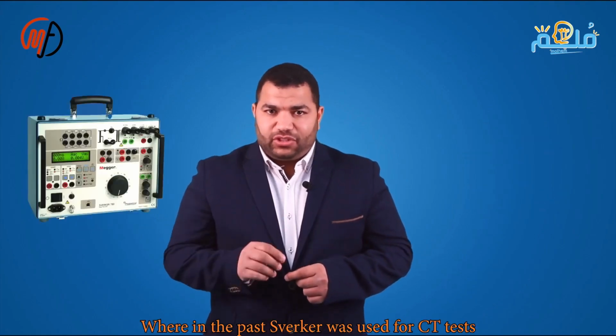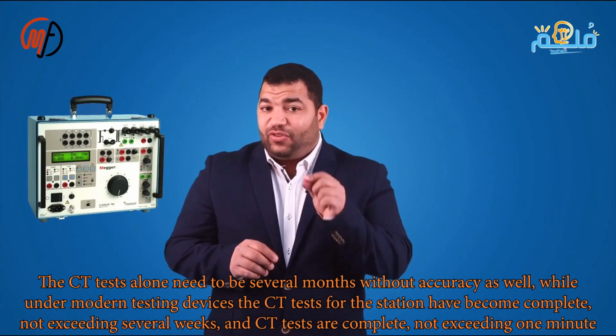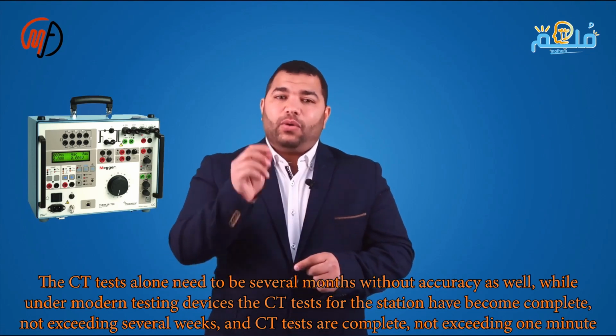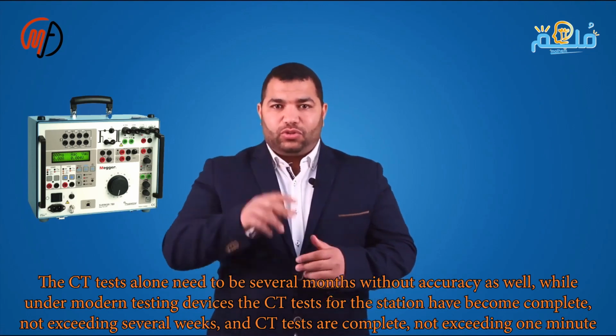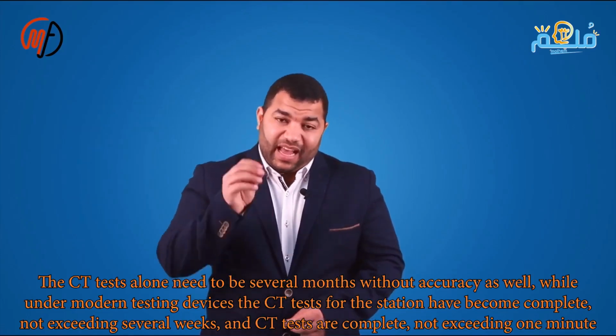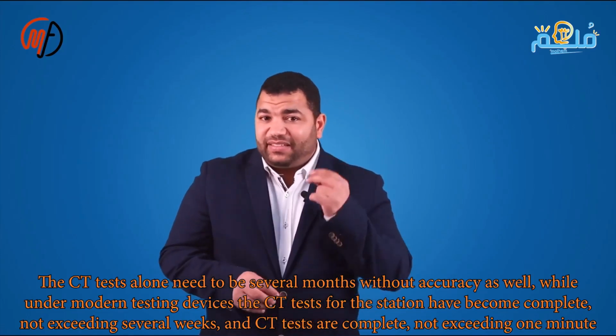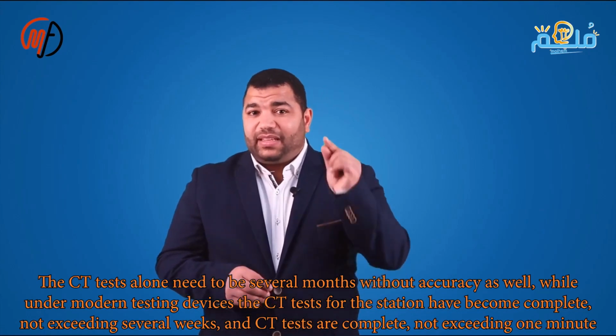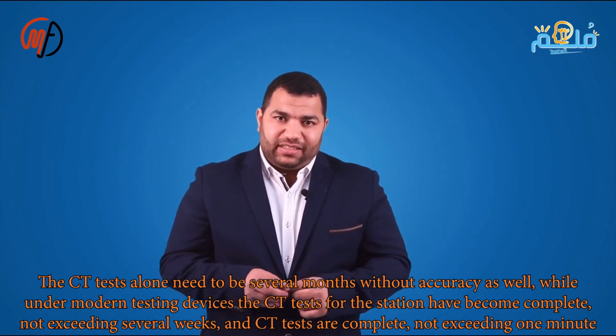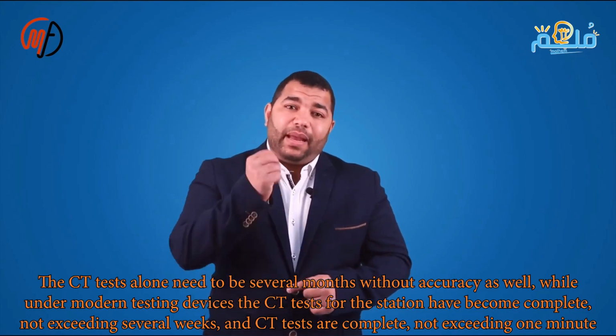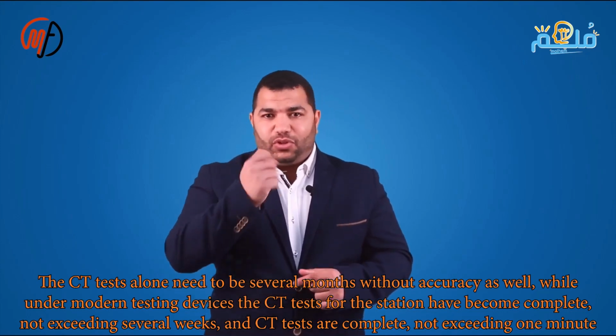Traditional testing faced issues like inaccurate CT ratio measurements due to conversion errors and load variations. High variable loads could damage CTs, leading to inaccurate reports. CT tests for the station have now become complete in just a few weeks, and full CT tests take less than a minute. There were many obstacles and issues during testing with traditional devices.